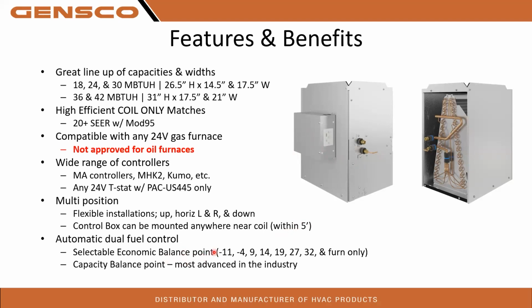Balance points are where the system switches from heat pump over to furnace. It's going to change a little depending on whether you're using a Hyper Heat or a standard heat pump. As you can see, we have a pretty wide variety of balance points, ranging anywhere from -11 degrees to 32 degrees, or furnace only if you're using a PUZ cooling-only system. With that, it's going to change a bit. The negative degrees are on the Hyper Heat units. 9 degrees and up is going to be on pretty much all of your units. That's the point at which your system switches from the heat pump to the gas furnace automatically based on outdoor temperature.